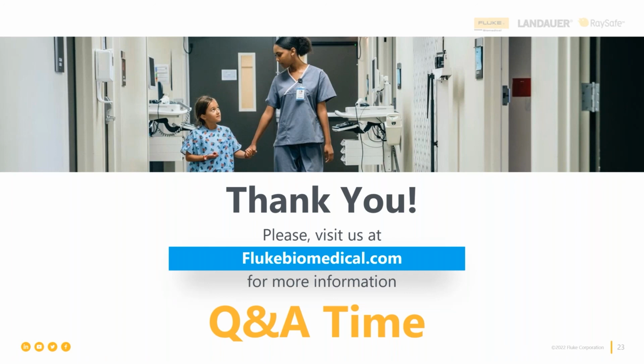Okay, thanks. Two more questions. So how does IEC 60601-1 shorten the life of the medical device? It's another good question. So the IEC 60601-1 requires that the protective earth resistance be measured using 25 amps of current flow.